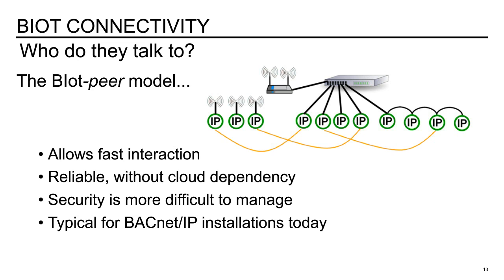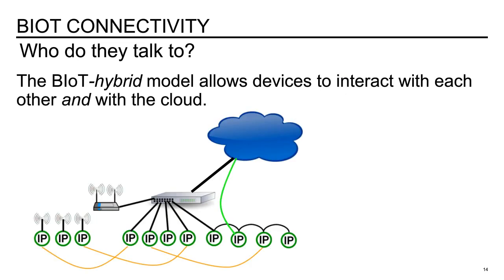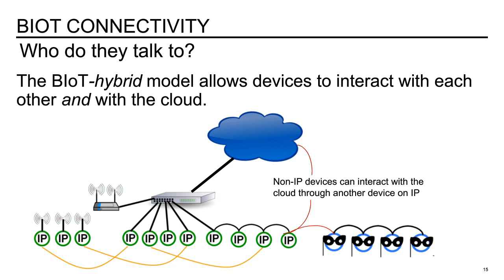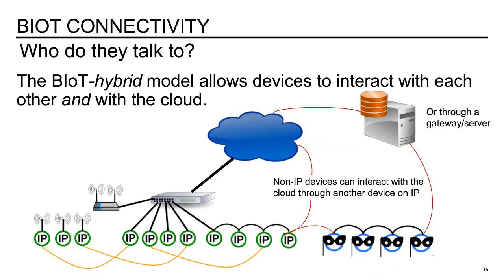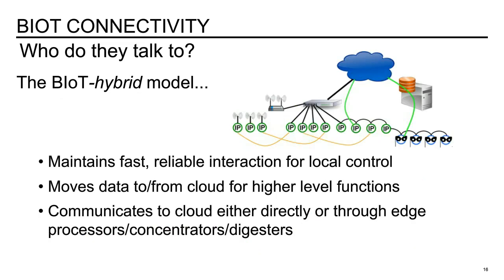So how do they talk to the cloud? The hybrid model allows devices to interact with each other and with the cloud. And then non-IP devices can interact with the cloud through another device that's on the IP network, or through a gateway or server that connects it to the cloud. The advantage of this hybrid model is it maintains fast, reliable interaction for local control. You're able to move data to and from the cloud for higher level functions. And then you communicate to the cloud either directly or through an edge processor, concentrator, or digester.